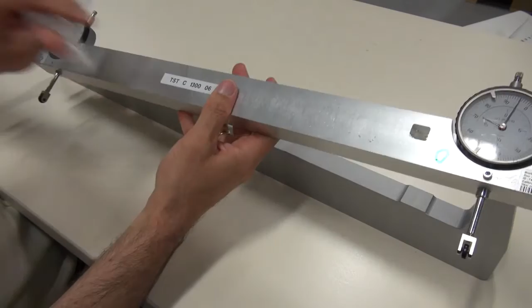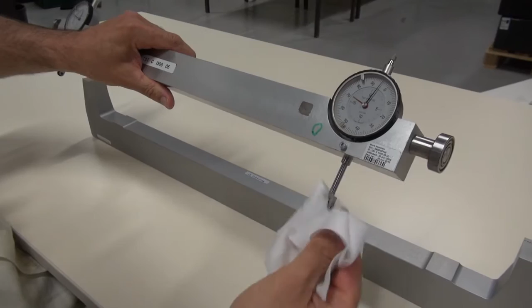The first thing we're going to do in order to calibrate this tool is make sure the wheels are clean and that they're not loose, that everything is fixed like it should be. Of course, not too hard fixed. The little pin should still be able to move, but all the little wheels need to be cleaned, and you check for general damages. Also clean the bearing and check for general damages on both sides.